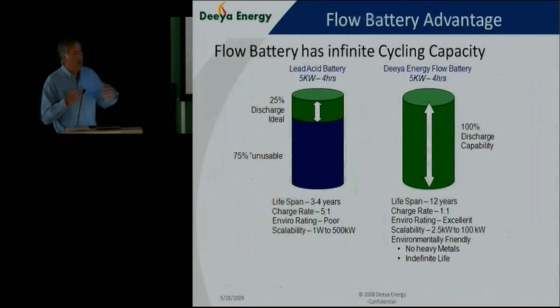The differences between our technology and incumbent lead-acid battery technology: traditional lead-acid batteries have a long history, over 100 years of development, and have essentially used the same chemistry that whole time. They have very little usability after you discharge the system to approximately 25%. You can go below that discharge cycling capacity, but it will always damage the battery and prevent it from charging back to the rate it had when new.